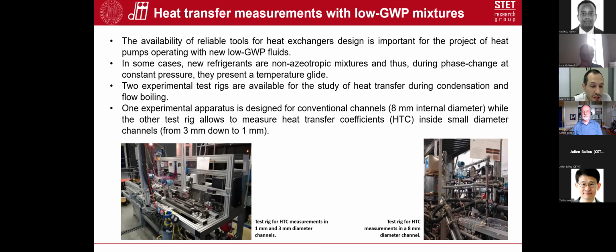It is also interesting to see that in some cases, new refrigerants are non-azeotropic mixtures, which means that during the phase change, there is a constant pressure, neglecting the pressure drop, but they present a temperature glide. Okay, so it is a gliding temperature process.